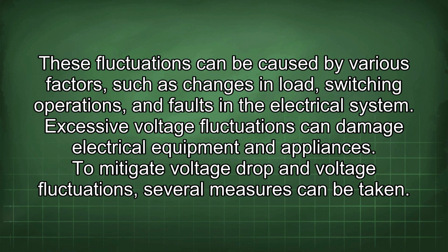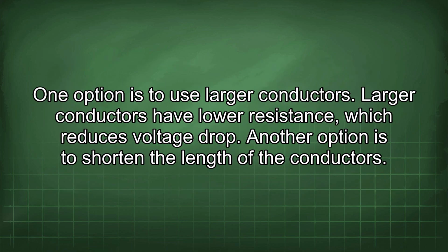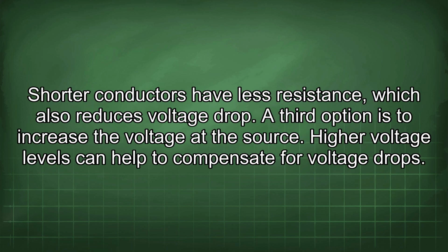To mitigate voltage drop and voltage fluctuations, several measures can be taken. One option is to use larger conductors. Larger conductors have lower resistance, which reduces voltage drop. Another option is to shorten the length of the conductors. Shorter conductors have less resistance, which also reduces voltage drop. A third option is to increase the voltage at the source. Higher voltage levels can help to compensate for voltage drops.